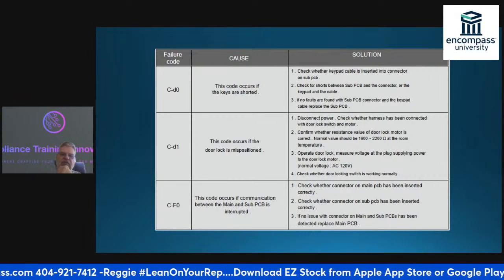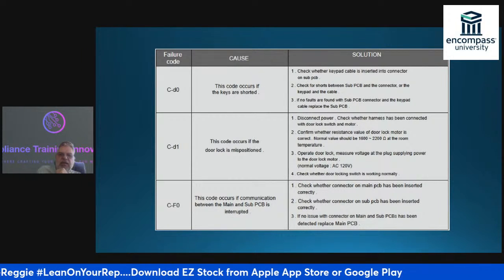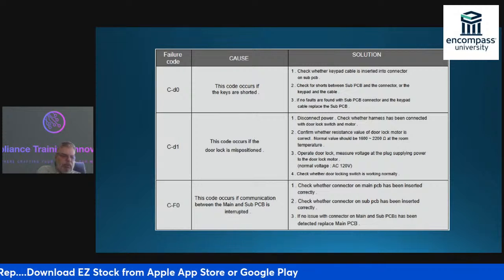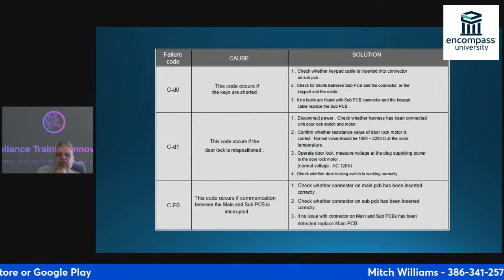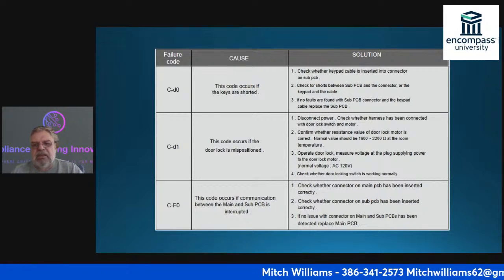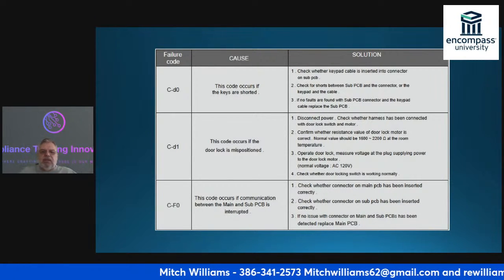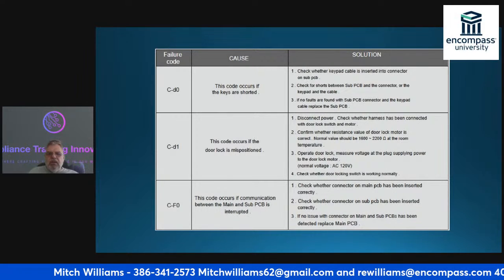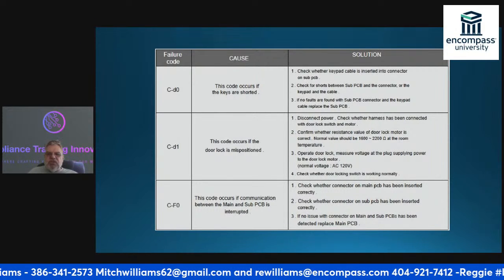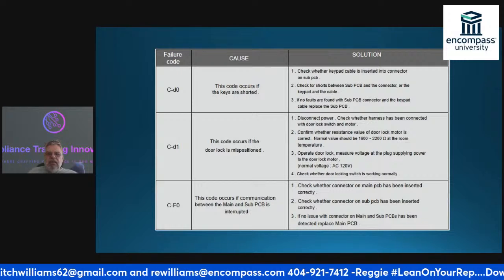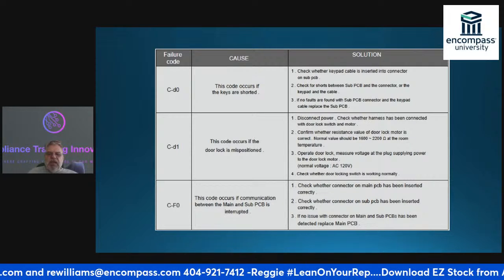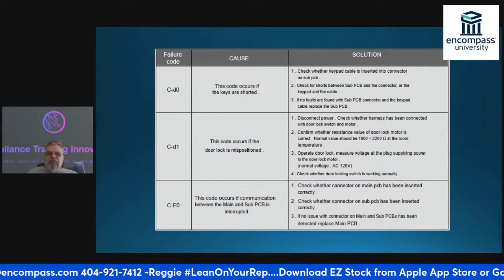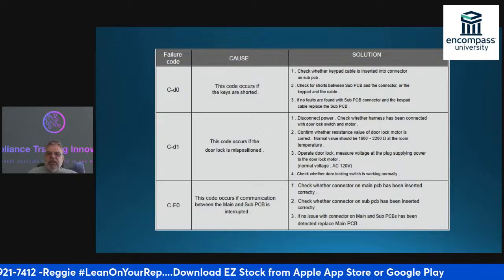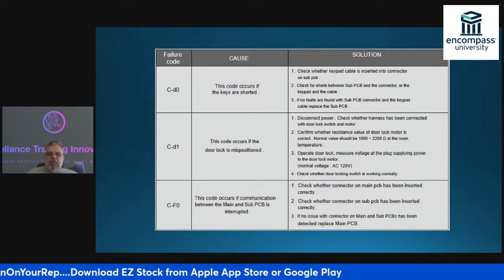If I have a C-d0, it occurs whenever the keys are shorted. So I have the keypad assembly that I have to look at. I'm going to check to see the keypad cable is inserted in the connector and the subassembly, and I'm going to check the shorts between the sub PCB and the connector or the keypad and the cable. If no faults are found with the subassembly connector and the keypad cable, you have to replace the PCB.